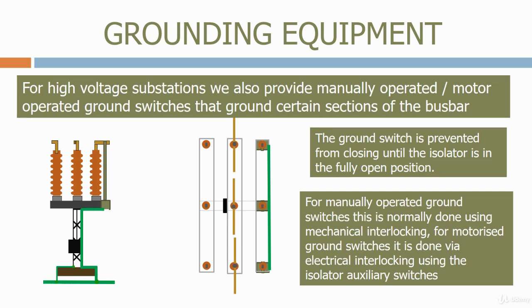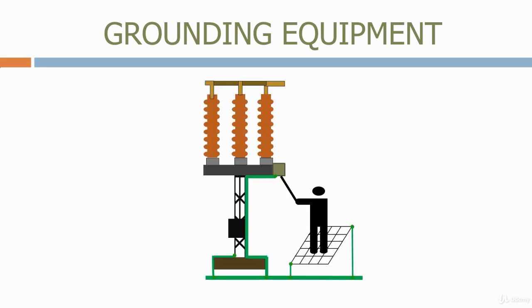When we have manually operated ground switches, we normally provide a ground mat for personnel to stand on as an additional safety feature. This ensures that the person's hands, which are in contact with the ground switch handle, and their feet are both at the same potential, so that if something does go wrong and the ground switch closes onto a live busbar, the current will flow through the ground switch ground connection rather than the person operating the ground switch.